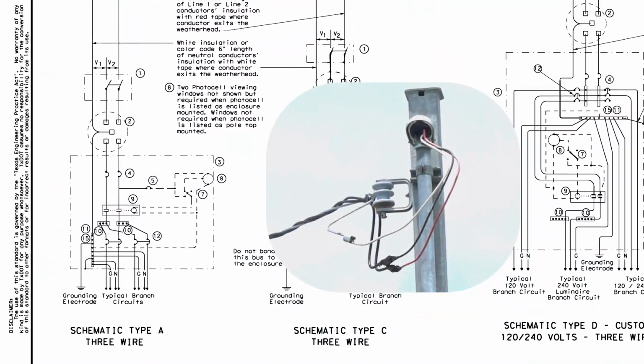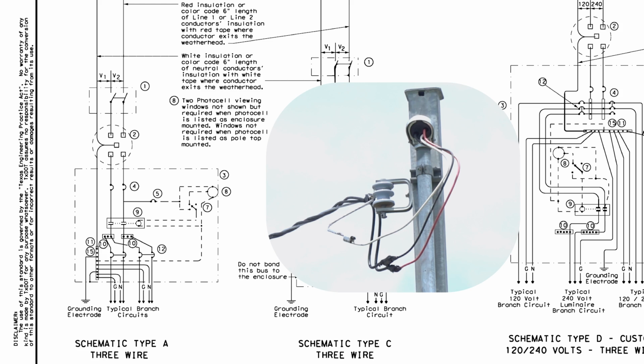The standard sheet ED6 shows a line drawing of a Type A electrical service and specifies that the three service entrance conductors be identified with red, black, and white insulation. For conductor sizes number 4 or larger, 2 black conductors may be re-identified with white and red phasing tape, with the third conductor remaining black insulated. The colored phasing tape should cover 6 inches of the conductor's insulation at every accessible location where the conductors can be seen.